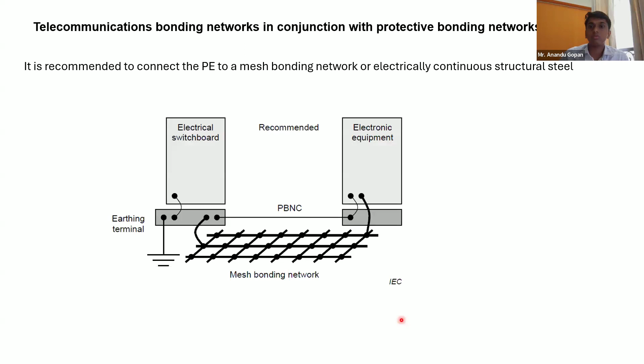So when you have these conductors connected between the METs of panel 1 and panel 2, preferably you also connect to the structural steel, electrically continuous steel, so that the EMI generated due to maybe a short circuit or some fault can be reduced through some current flowing through the continuous structural steel also. This steel must be electrically continuous, so you have to make sure of that. And in the upcoming slides, I will be explaining about EMI, EMC and how you can prevent it through this kind of network. Basically, when you connect all of this to the structural steel, and you connect your telecommunication also to the structural steel, you will follow a mesh bonding network, which is coming in the upcoming slides.